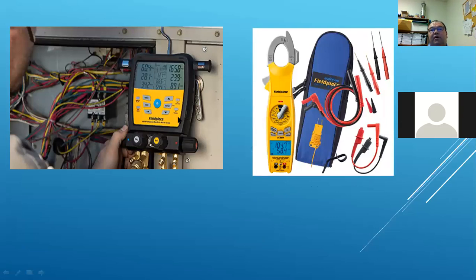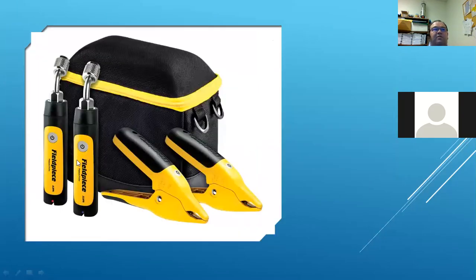As you get into Fieldpiece, I do like Fieldpiece. Used their meters for years. You get into the higher end Bluetooth that you can link to JobLink. You can use your meter for JobLink. This digital manifold will link to JobLink as well as these Bluetooth gauges. So if you have any combination of those, they also have the Bluetooth temperature probes, which will link into JobLink that will give you a complete picture of what's going on with the system. Plus, you don't lose any refrigerant because you're screwing directly onto the service ports.